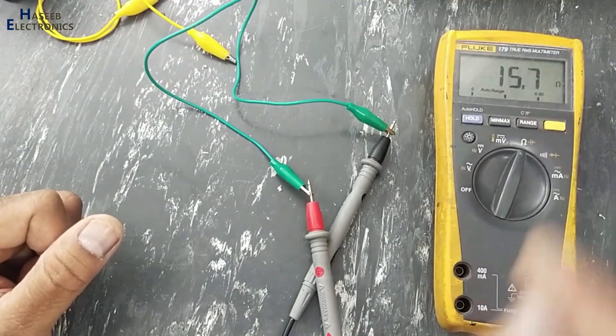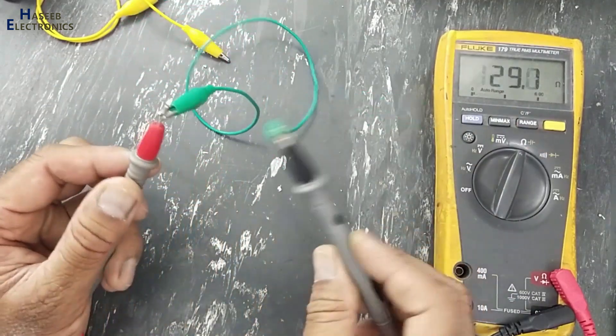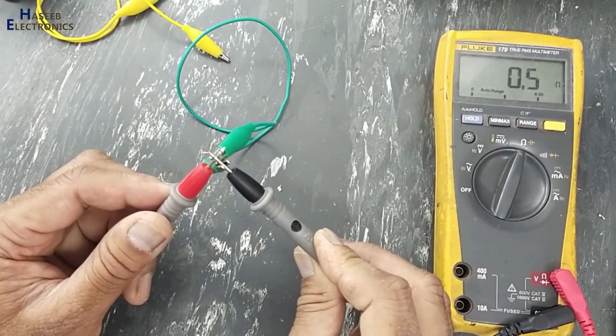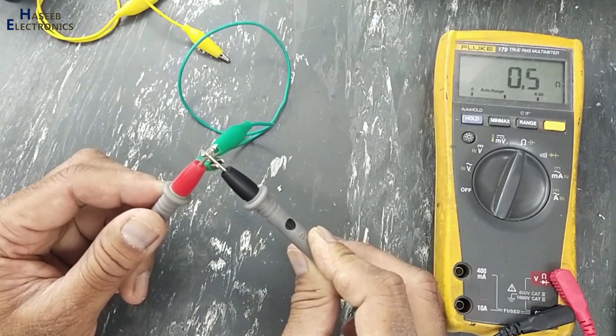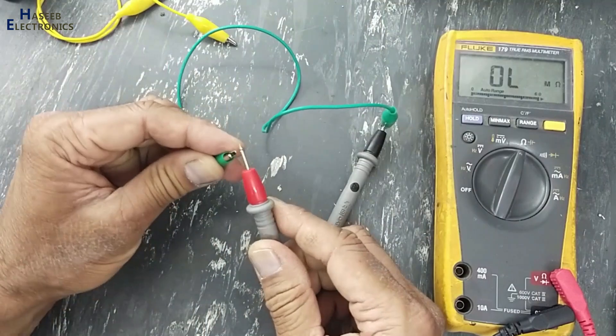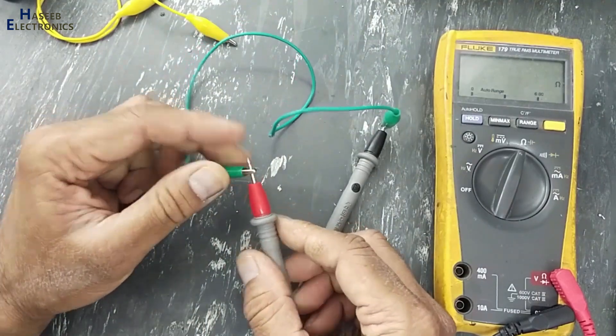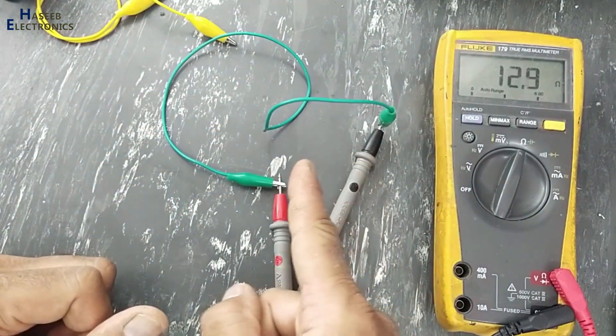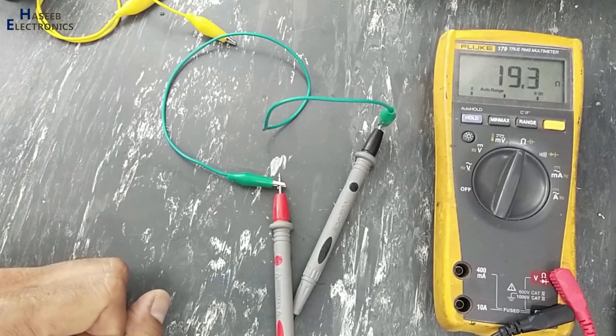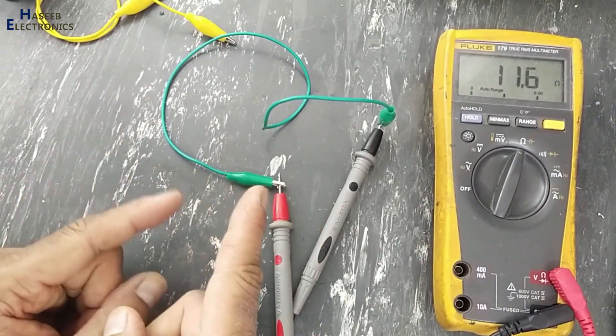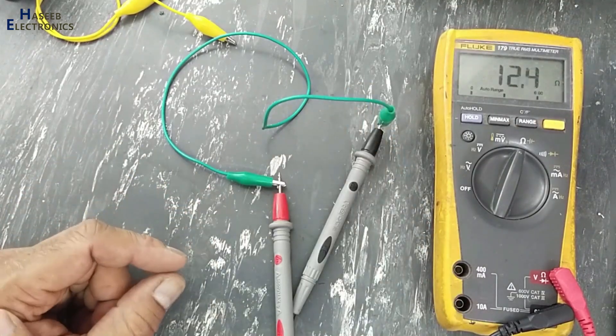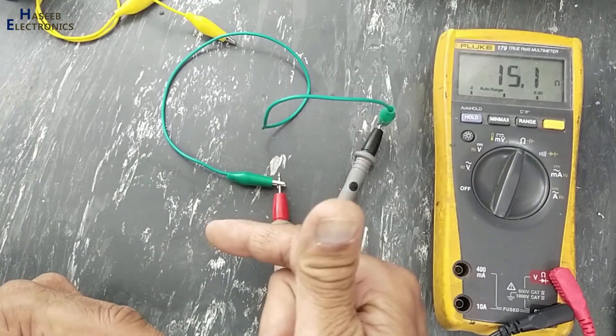It is showing 12 ohm resistance, but if I connect here the multimeter is 0.5 ohms. So this wire is bad. If connected in any circuit, it will drop the signal. What is the resistance that will be produced in the circuit?